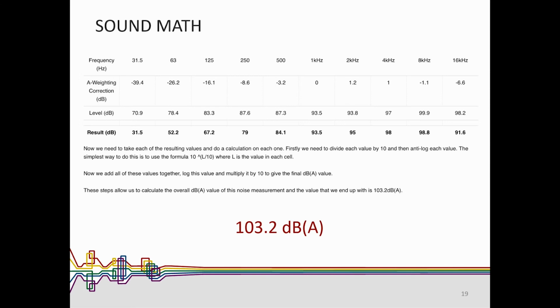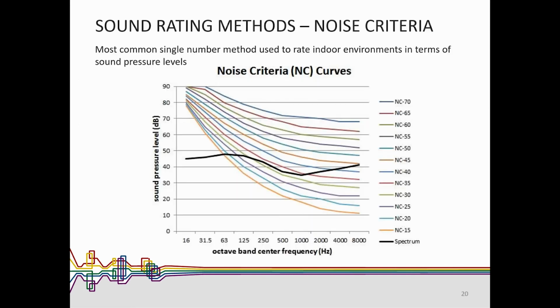So that was very quick into dBA, dBc, and dBs and octave bands. Now the other kind of thing that you have to worry about when we're talking about B3 is NC. So you say, well, we have all these other things, why can't we use those? What is NC? So NC is another way of looking at it where we've taken, again, a sort of evaluation of what somebody would say is reasonable in a space. And in this case, we've plotted a sound that you're measuring using an octave band meter, and you look at every frequency, and basically the NC curve that it is below is the NC you have. So in this case, this is an NC 45 space.